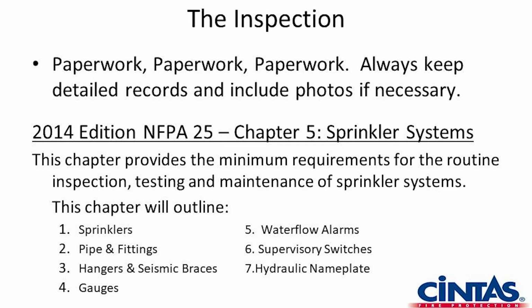This covers the sprinklers and the alarms, the pipe and fitting, and the switches on the system that will communicate with the fire alarm panel. We're looking at the hangers, and if we are in a seismic area, the seismic bracing. Things become loose after years, and those are things that we're looking for. I apologize for number 4 being cut off.